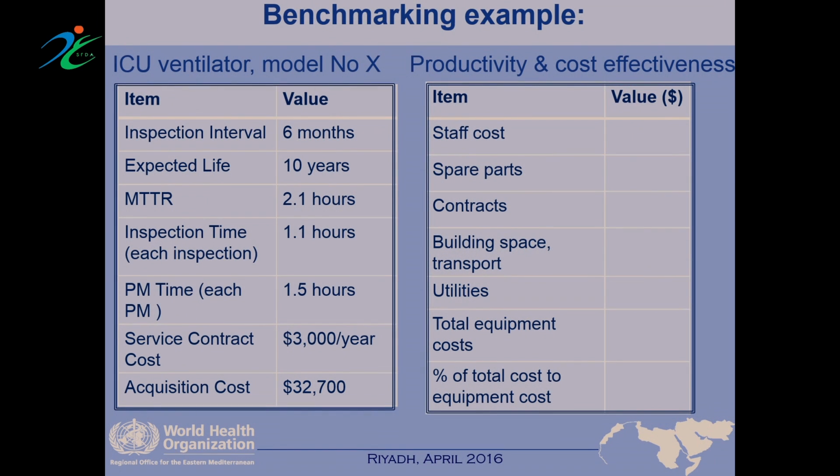The mean time to repair calculated at that hospital is 2.1 hours, and the inspection time is calculated at 1.1 hours. When these data are collected, you can compare yourself to other countries and other hospitals. And then you see here the figures that you need: approximately how much the service cost is versus the acquisition cost.